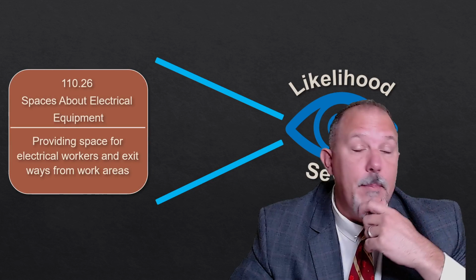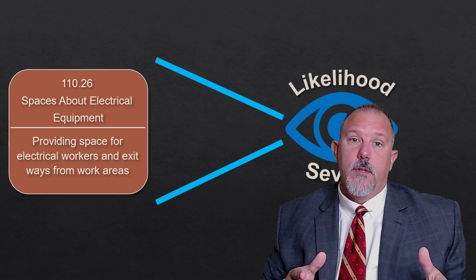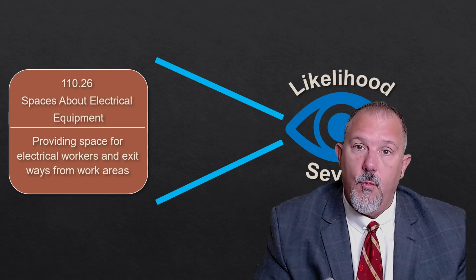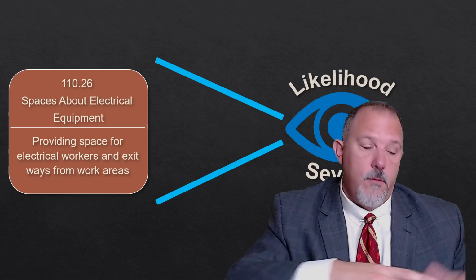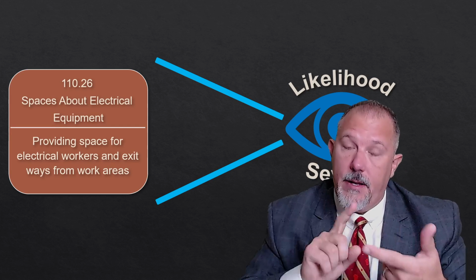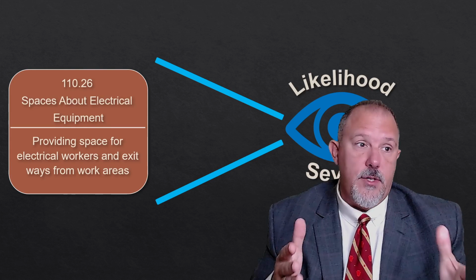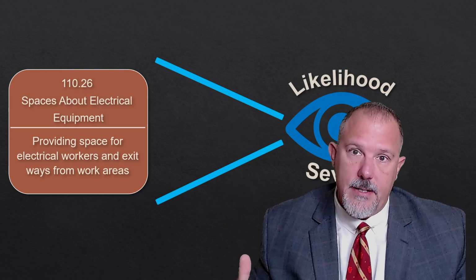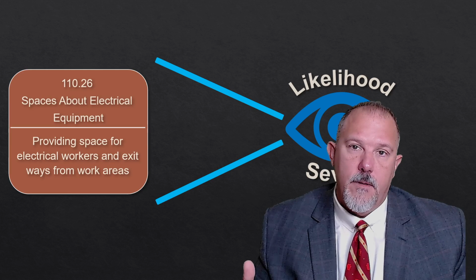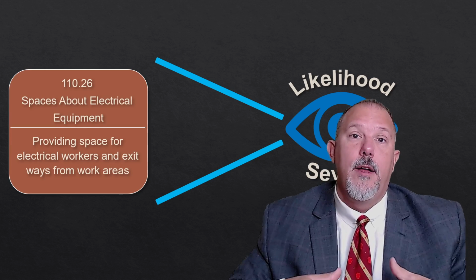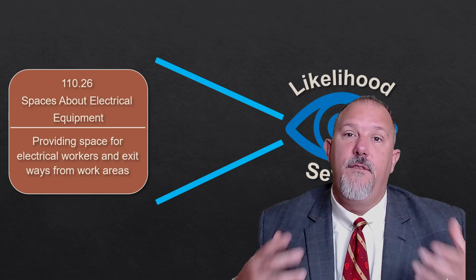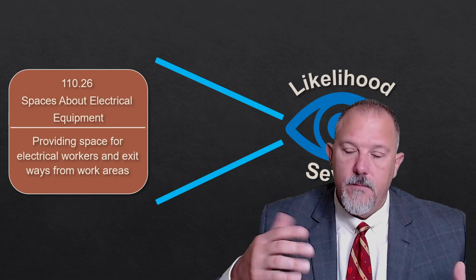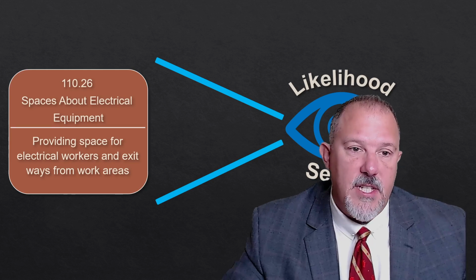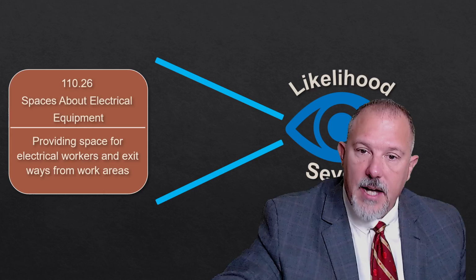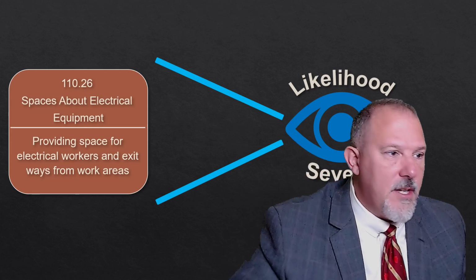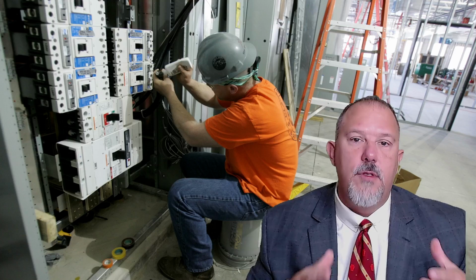That is, in my opinion, a great example of reducing severity. We've taken the same fault, non-protection with protection, and remember that equipment applied per the code is operating and functioning as designed. It's providing that delay. But when you have a problem and you start to have an abnormal event and you let the energy out, you can have that type of a problem. Working space. Space about electrical equipment gives us the ability to reduce the likelihood. Why? Because if I give the electrical workers space to do their job.